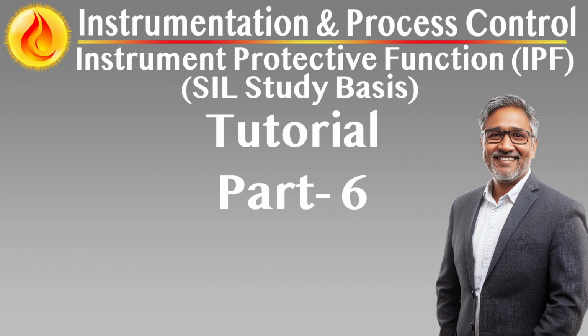Status display in central overview screens. A summary of all active overrides should be available on process overview pages, not buried in submenu navigation. Procedural alignment with operations. Pre-override briefing. Prior to applying an override, operations and maintenance teams must jointly review the purpose, process impact, required compensating measures, and escalation plan.